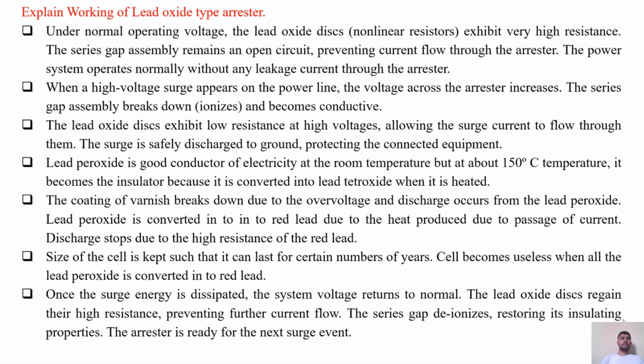Explain working of lead oxide type arrestor. So under the normal operating voltage, the lead oxide disc, that is the non-linear resistor, exhibits a very high resistance. The series gap assembly remains an open circuit, preventing the current flow through the arrestor. The power system operates normally without any leakage current through the arrestor during this normal operating voltage condition.